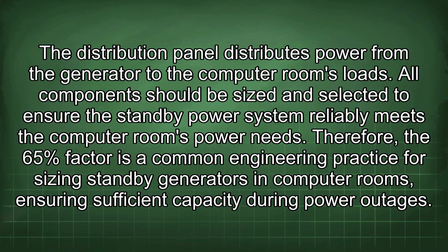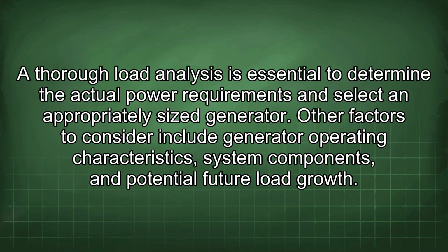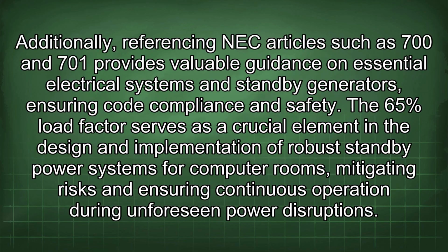Therefore, the 65% factor is a common engineering practice for sizing standby generators in computer rooms, ensuring sufficient capacity during power outages. A thorough load analysis is essential to determine the actual power requirements and select an appropriately sized generator. Other factors to consider include generator operating characteristics, system components, and potential future load growth. Additionally, referencing NEC articles such as 700 and 701 provides valuable guidance on essential electrical systems and standby generators, ensuring code compliance and safety. The 65% load factor serves as a crucial element in the design and implementation of robust standby power systems for computer rooms, mitigating risks and ensuring continuous operation during unforeseen power disruptions.